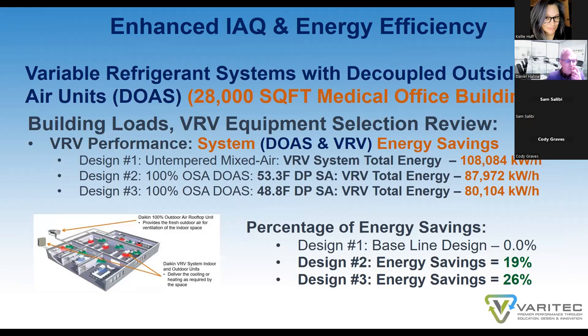The study was comprised of three variable refrigerant design configurations. We see it regularly here in Phoenix, Arizona, where variable refrigerant technology uses an untempered outside air source for the outside air to a building. That is to say, we just bring outside air into the air handlers of a variable refrigerant system to mix with the return air drawn by the unit. Then we did two studies of a parallel 100% outside air system where the outside air unit and duct is decoupled from the variable refrigerant system. And we did it at two supply air conditions off the dedicated outside air unit, one providing air at a dew point of 53.3 degrees, and the second providing a lower, drier air condition of 48.8 degrees dew point.